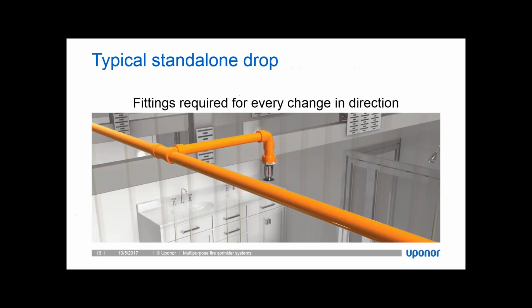This is what a typical CPVC drop installation would look like. So I have my main line running to a branch line, so I need a T to get over to that drop. And then once I get to that drop, I need another sprinkler adapter. So if I'm looking at the connections on this, at the T, I've got 3 cement connections. At the drop, I have 2 cement connections for that elbow, and then I've got 1 additional cement connection where that sprinkler adapter is. All of this piping can be dry fit.